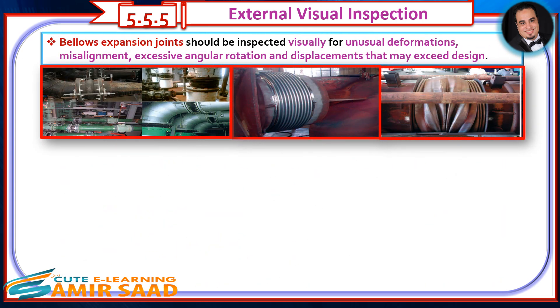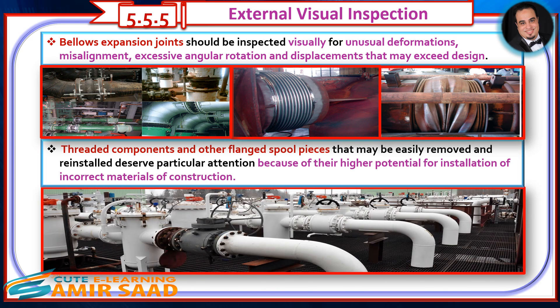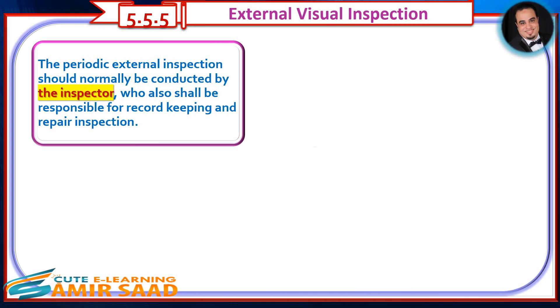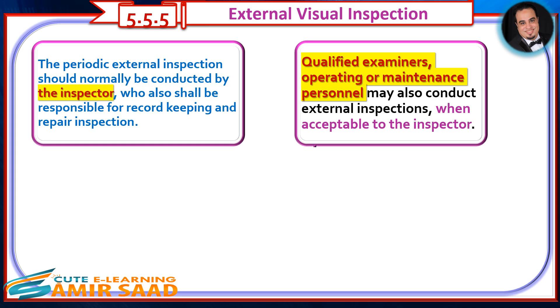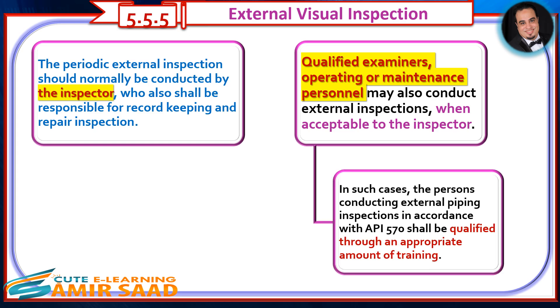Bellows expansion joints should be inspected visually for unusual deformations, misalignment, excessive angular rotation, and displacements that may exceed design. Threaded components and other flanged spool pieces that may be easily removed and reinstalled deserve particular attention because of their higher potential for installation of incorrect materials of construction. The periodic external inspection should normally be conducted by the inspector, who is also responsible for record-keeping and repair inspection. Qualified examiners, operating or maintenance personnel may also conduct external inspections when acceptable to the inspector, provided they are qualified through appropriate training per API 570.